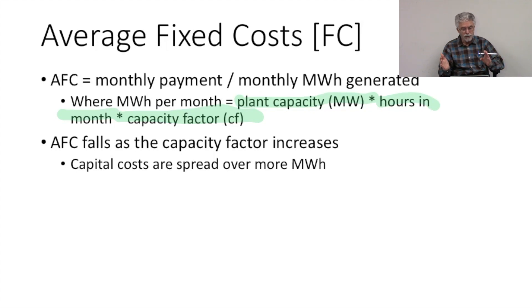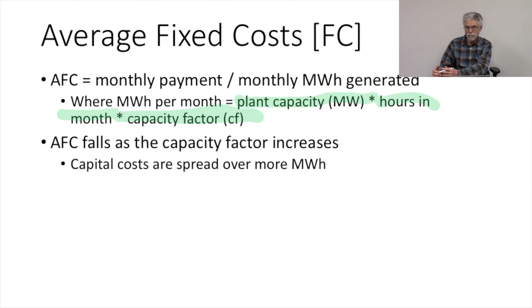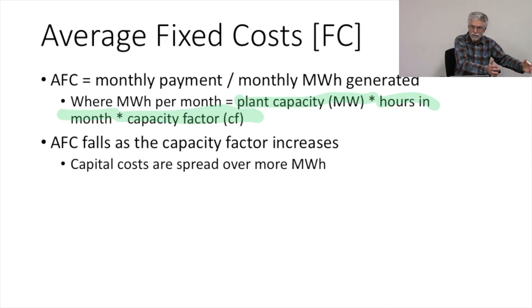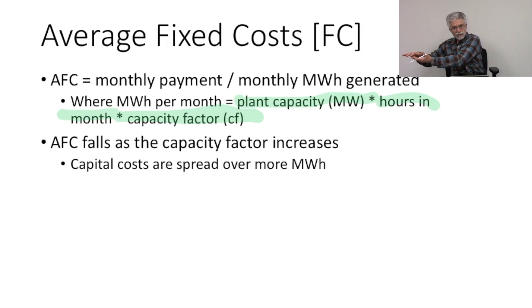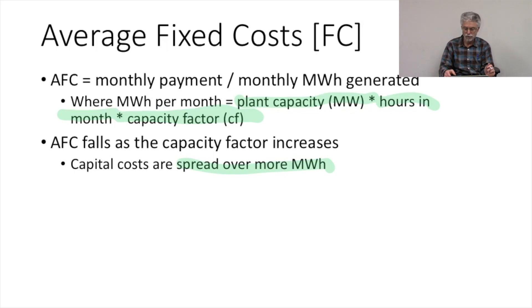It's clear from this calculation that average fixed cost will fall as the capacity factor of the plant increases. As capacity factor increases, that increases the megawatt hours we generate. Our monthly fixed cost stays the same, so the more we generate, the more we're dividing into those fixed costs, and the fixed costs tend to fall as we run the power plant at higher and higher capacity factors. The capital costs are spread over more megawatt hours, so the average fixed costs fall.